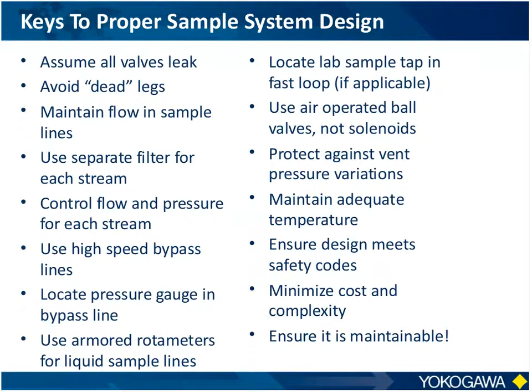So to do this, the first thing the system integrator is going to do is start asking you a lot of questions. So you need to prepare to answer things like, what is the total chemical composition of the stream? And not just during normal situations, but also during upsets. A situation occurred some years ago where we were building a sample system to monitor a stream in a refinery, and the customer forgot to tell us that during upset conditions, HF acid would be present in high concentrations. And unfortunately, the first time that happened, literally all the stainless steel within the sample system and analyzer dissolved.